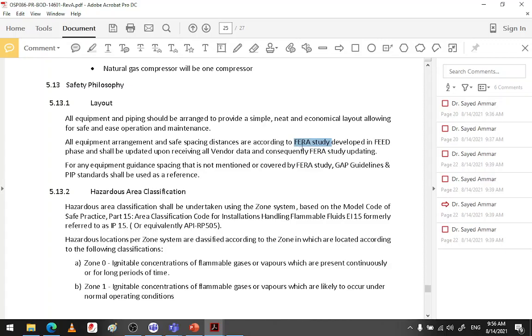Fire Explosion Risk Assessment Study. This will be done by PHAST software to say if this separator, for example, has a pinhole and we get a jet fire, the impact of this jet fire on the nearby equipment. For example, if the flame length of this jet fire reaches 12 meters, we should install the equipment beside the separator at a distance of 13 meters, 1 meter above the flame length. This is output from the FERA study.